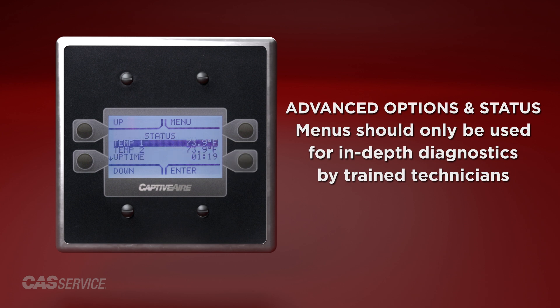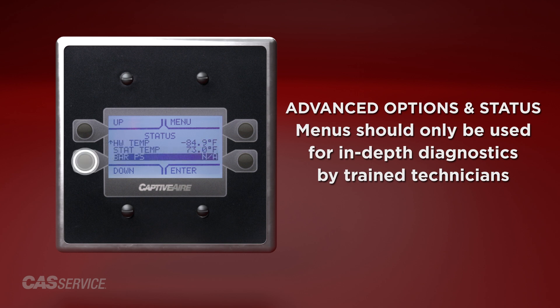The advanced options and status menu should only be used for in-depth diagnostics by trained technicians. In these menus, you can view real-time temperatures, relative humidities, uptime, and HMI data, as well as assign offsets to those values to further tune that HMI's precise control over space conditions.